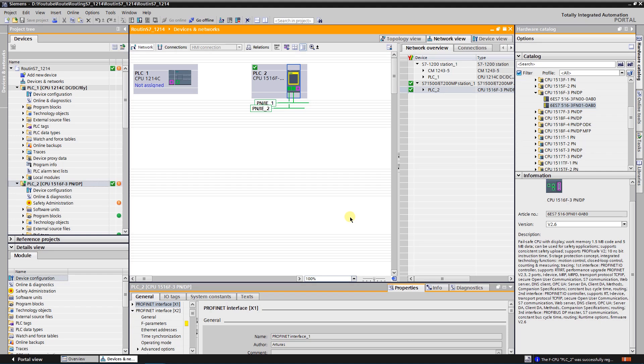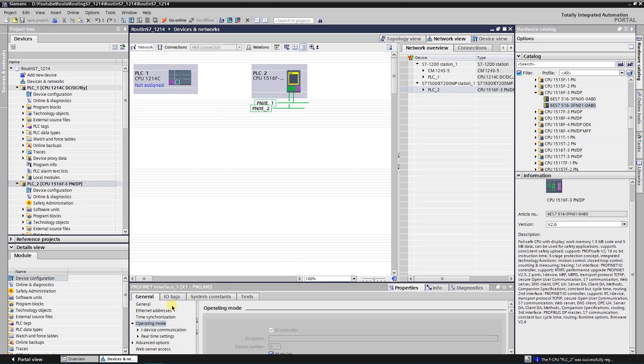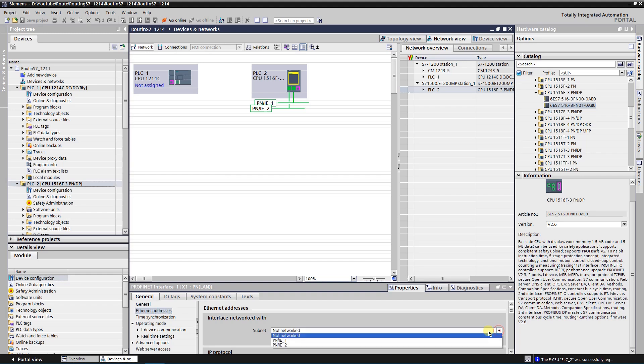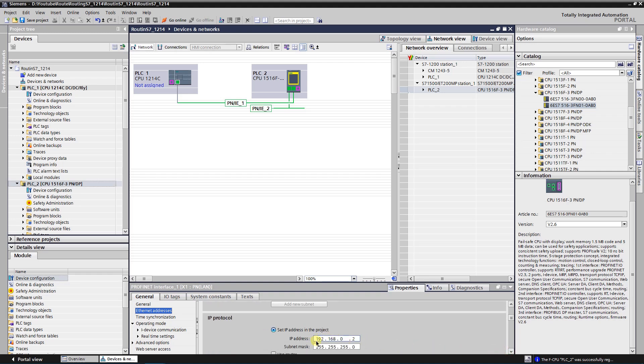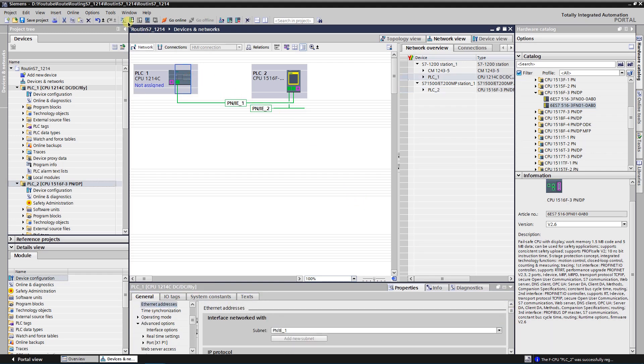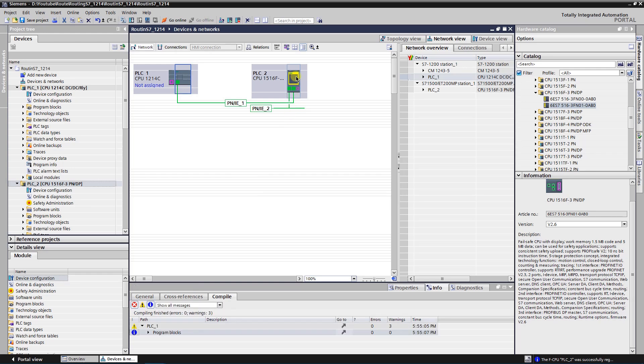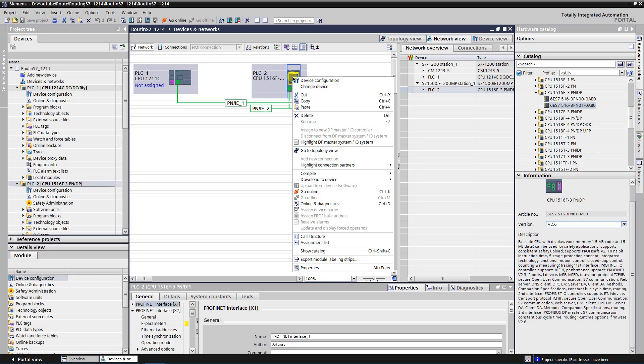Select the PLC and click on Go Online. Connection to the second PLC is established successfully. Select your first PLC and assign it to the subnet PNIE1. Check if the IP address is correct. Compile and save your configuration. You need to download the hardware configuration before you try to connect to the first PLC. Select your second PLC, right-click on it and select Download to Device, then Hardware Configuration. Wait until the process is finished.